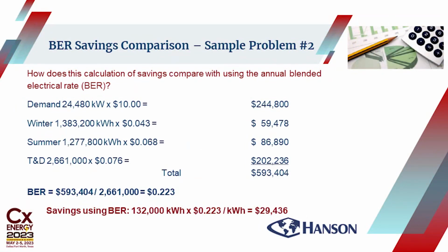People like to use a blended electrical rate, so let's do it the other way. Blended electrical rate uses the annual total consumption, okay? So here we've got the total demand for the year, 24,480, $10. Winter, summer, those are the totals. Transmission distribution, you don't include tax when you do this calculation for blended electrical rate. You come up with a total, you divide it by the total consumption in kilowatt hours. Your blended electrical rate is 22.3 cents.